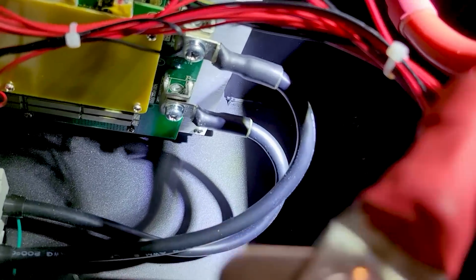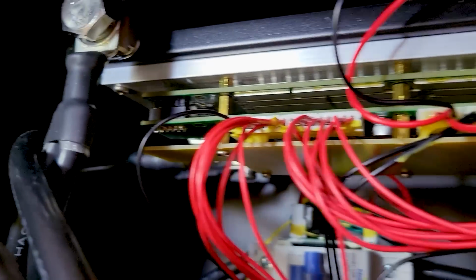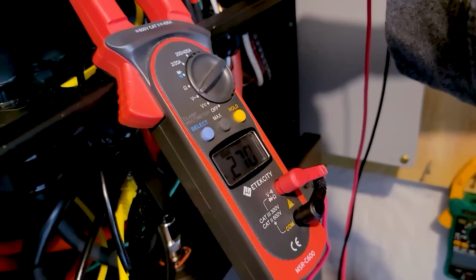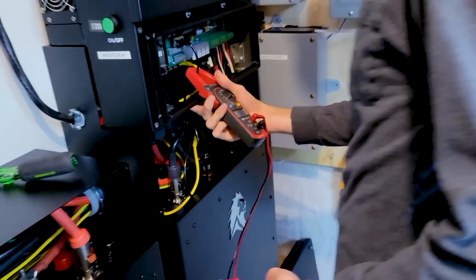If I am to install these inverters and batteries on a new install, I would absolutely do DC coupled. It just makes sense as compared to doing an AC coupled setup. The fact that we can AC couple solar into these inverters is excellent because it provides a great means for folks to retrofit existing solar systems to add this battery system. But absolutely from the get-go, if we're installing this on a new project, we will be DC coupling them.